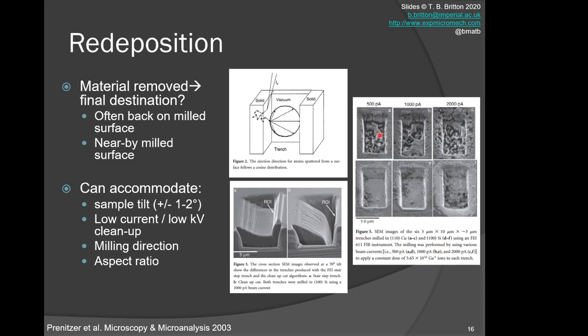We can also control the currents that we do the milling. With very high probe currents, we can see there is a much rougher mill and less good surface finish. This is much quicker because there's a higher probe current, so we can improve the quality by polishing at a lower probe current, and we could also do perhaps in certain instances a low kV final polish.